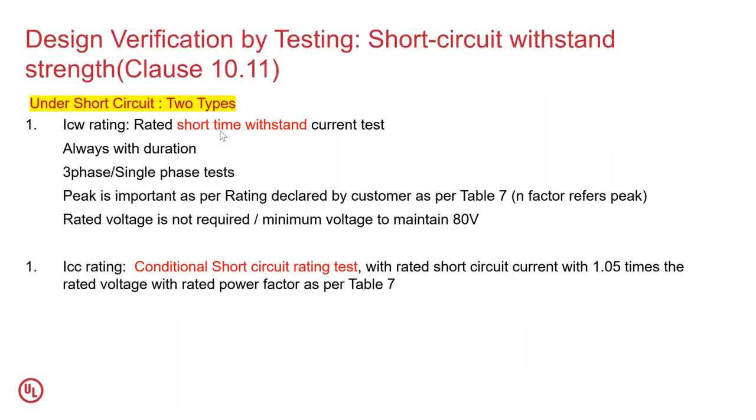And for the short time withstand current test, again, we go with three phase, because we talk about only four parameters in a switchboard, my dear guys: three phase, neutral, ground, nothing else in the switchboard. Three phase RYB or L1, L2, L3 plus neutral plus PE conductor. Means for the short circuit also, we need to consider all three phase RYB or L1, L2, L3 plus neutral plus protective conductor.